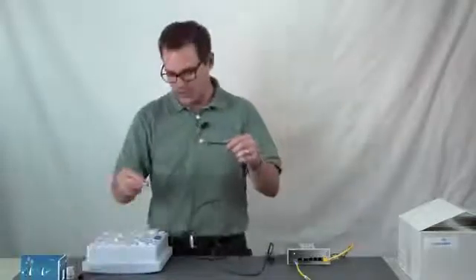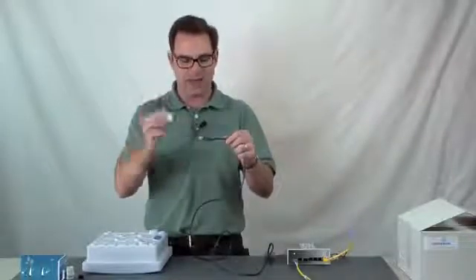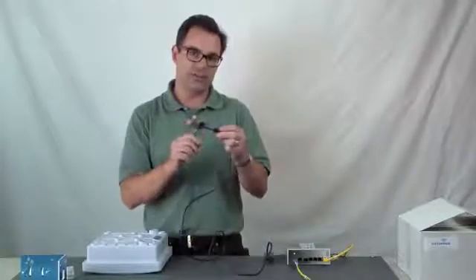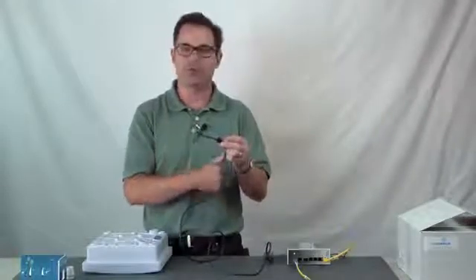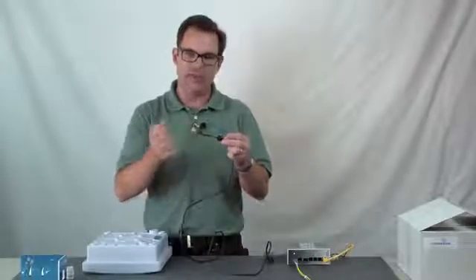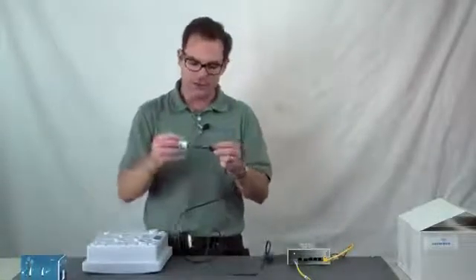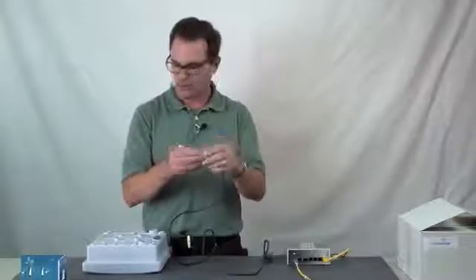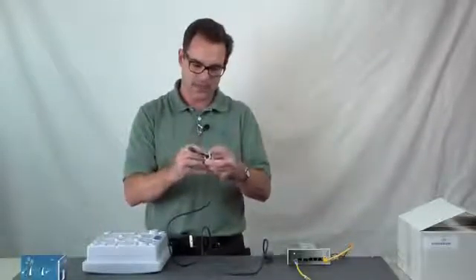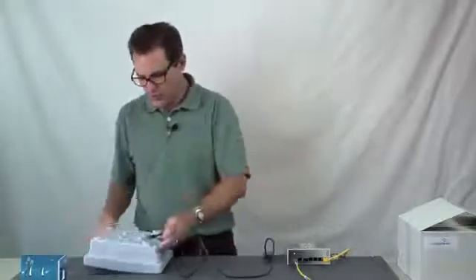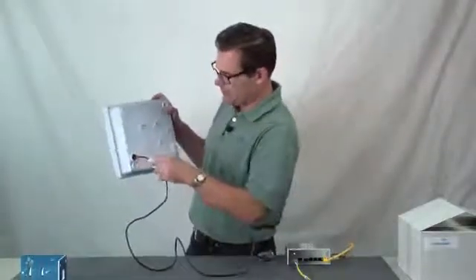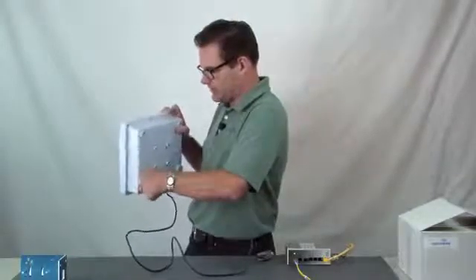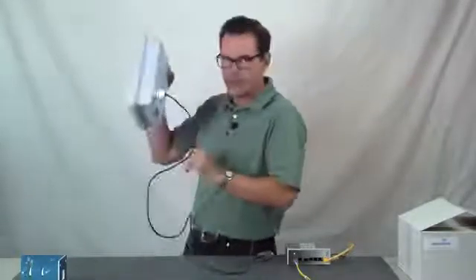We will start to put together our gland. You're going to work backwards. Your final cap is going to go on first, then the rubber gasket. This is a pre-terminated cable, which is a great feature, so you don't have to put through an unconnectorized cable and add the connector after. Next, we put the main portion of our gland on, screw that down, add an additional gasket, and mount all that together. Then we plug that into our RJ-45 and screw that gland down. Now we're IP67 rated.